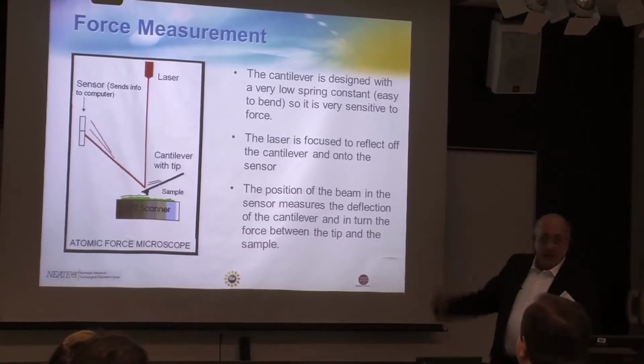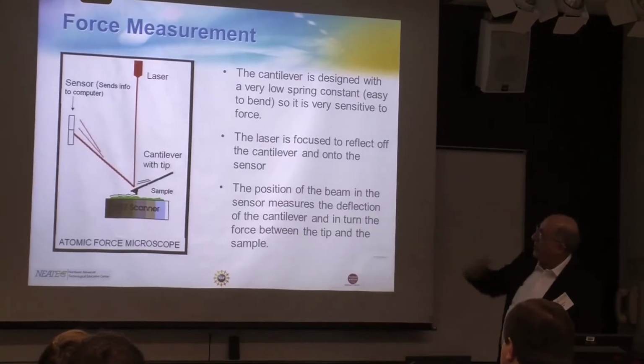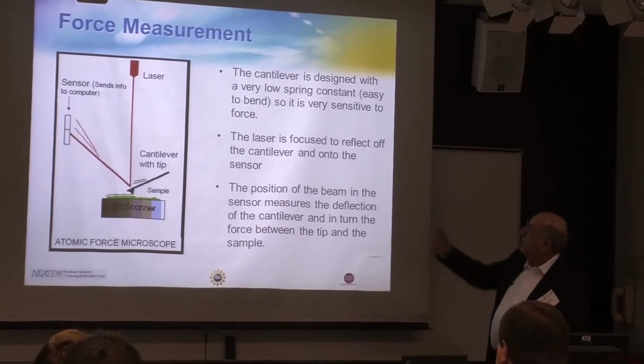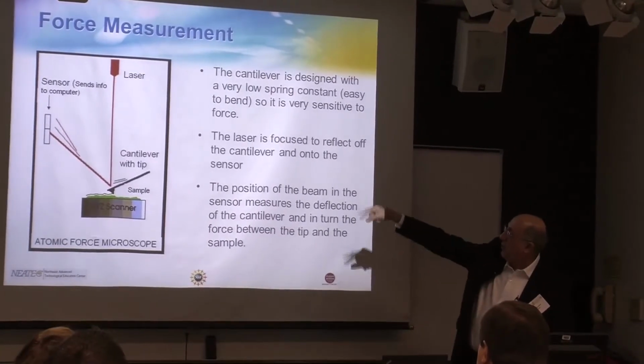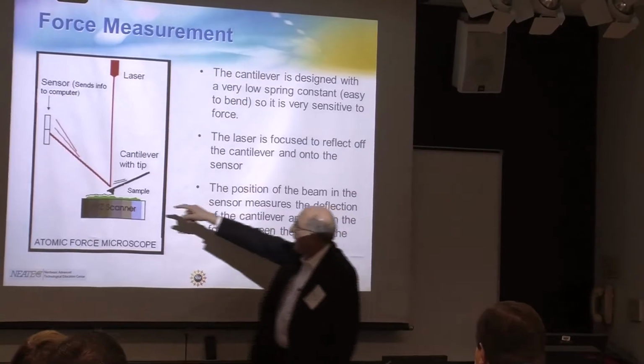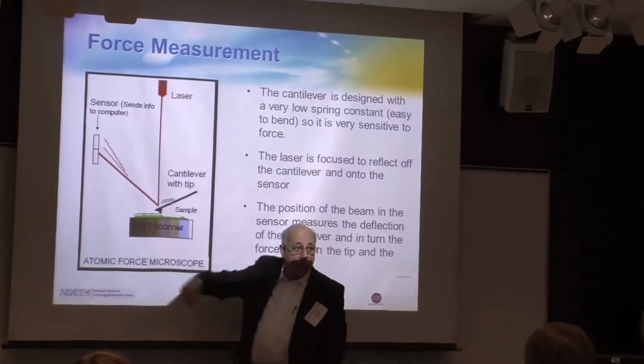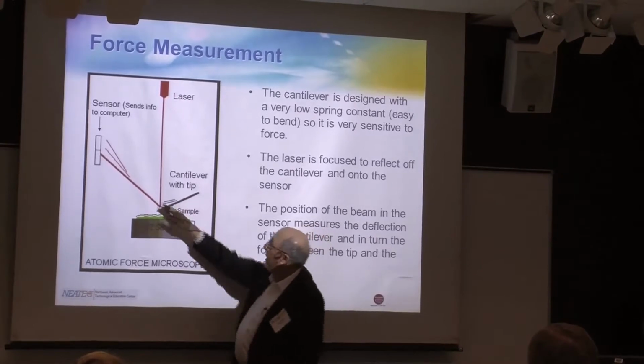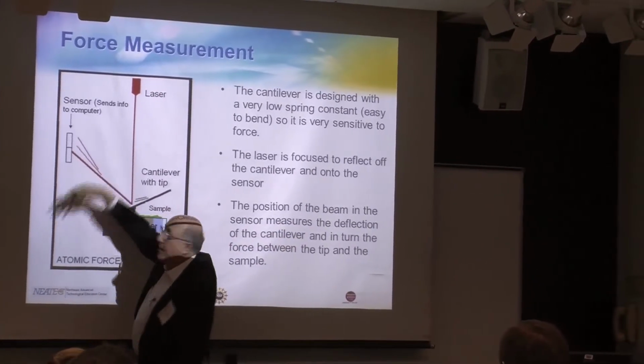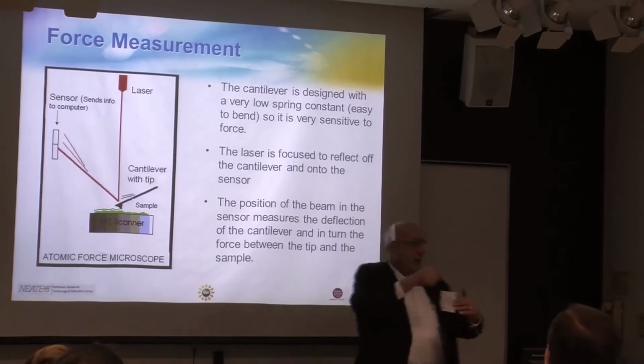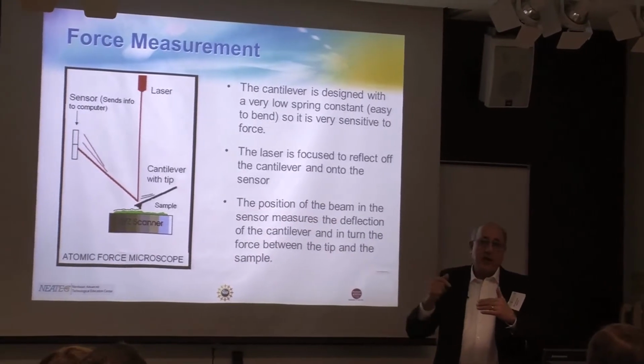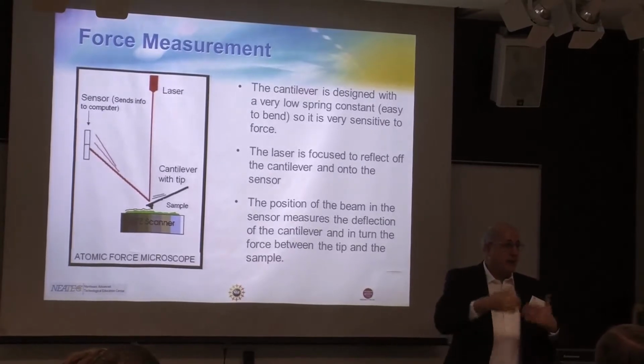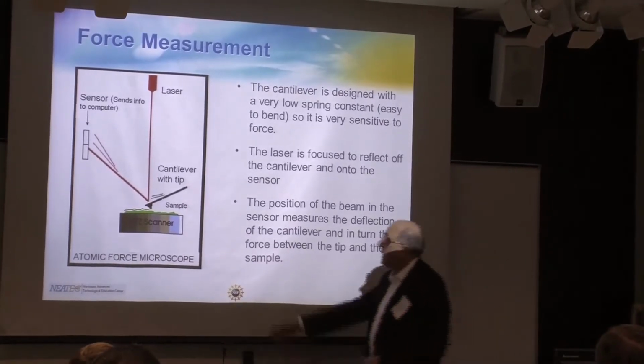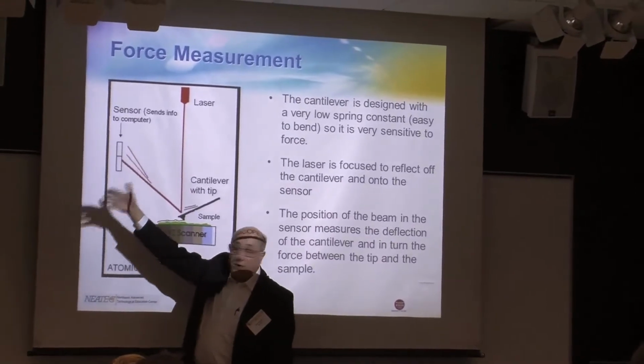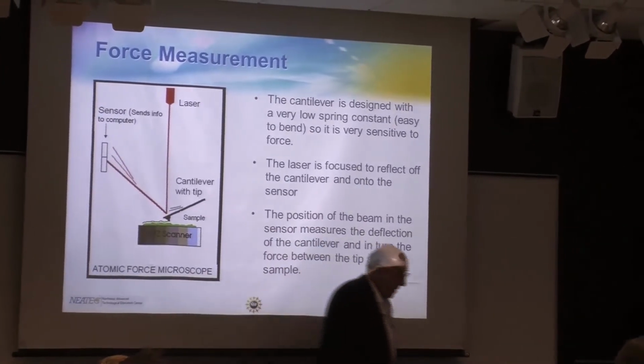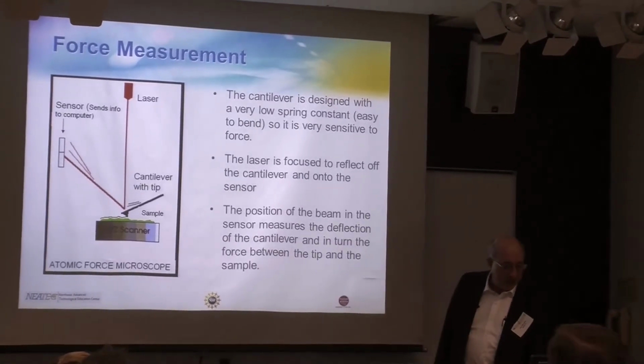I'm not going to go through this a lot, but you should see how we can measure force here. Basically, we measure force with a laser beam, and the force will depend on the position of the tip. The light will change here. With a mirror, the beam will impinge on different parts of this mirror or collector, and we have a calibration curve, so we know exactly what the force is. If it is impinging here, we can find out the force and so forth. So this is the way to measure force indirectly.